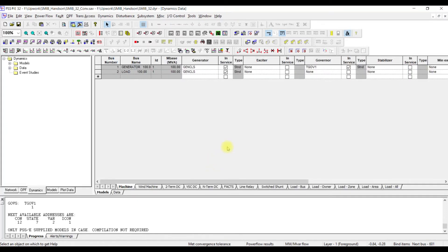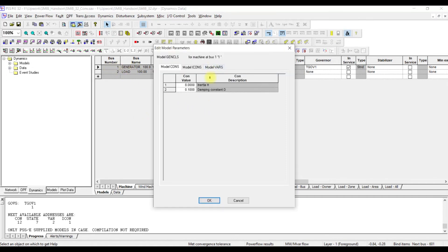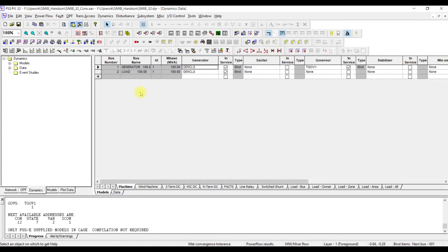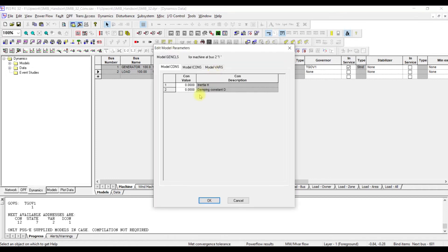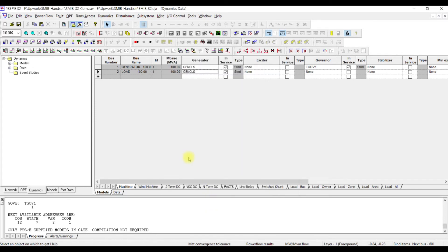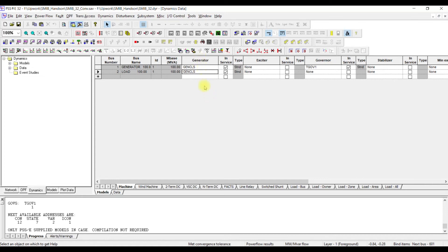Now, here you see a new file is created. For generator, we have a model GENCLS having an inertia of 8 and a damping constant of 0.1. Similarly, if you double click on this load, the generator which was connected on the load side, or which we call the infinite bus, here we are not using an inertia because it is an infinite bus. We want it to be infinite. So, without any inertia, it gives the maximum possible value. Here, one governor model is also used but we are not interested in governor model right now. Please leave this. We are only interested in the generator model because we are performing classical transient stability analysis. Once this is done, the first thing you have to do is let us save this file.